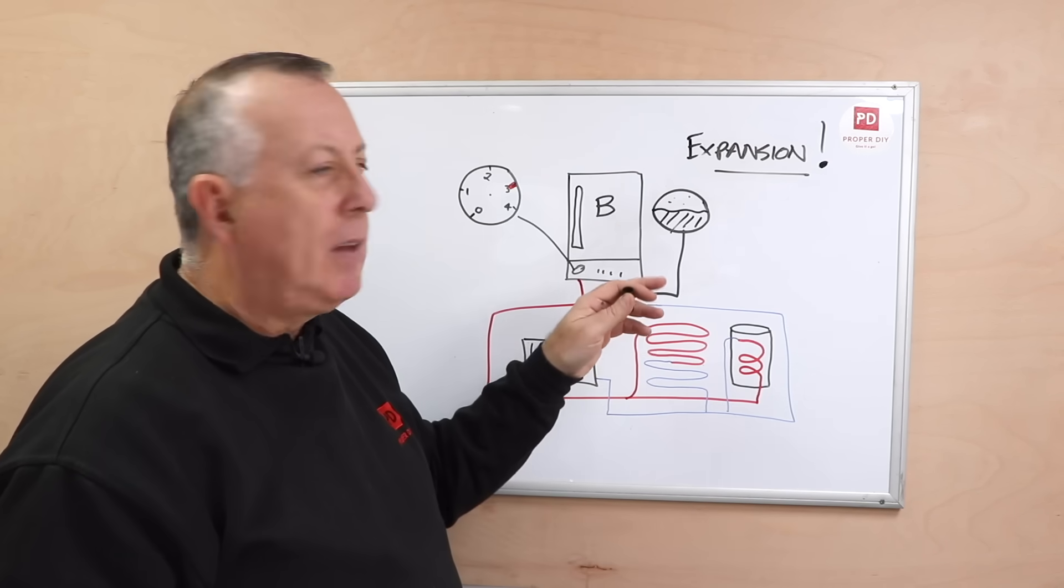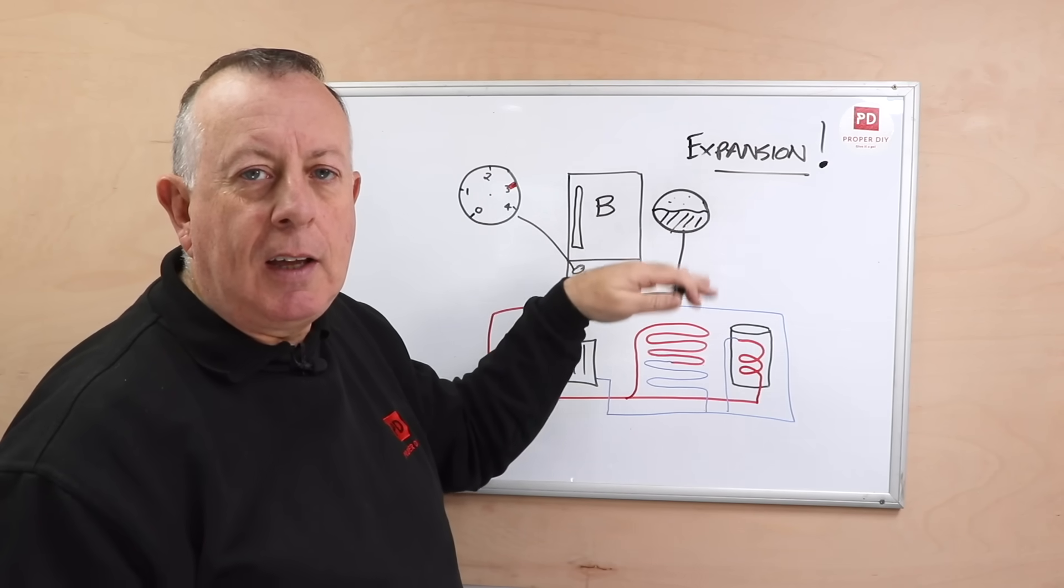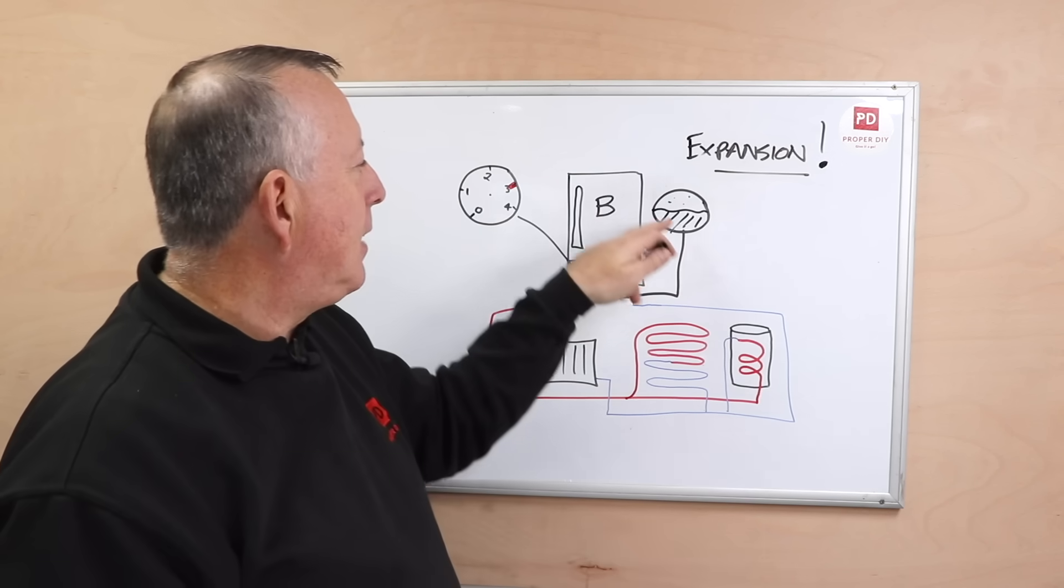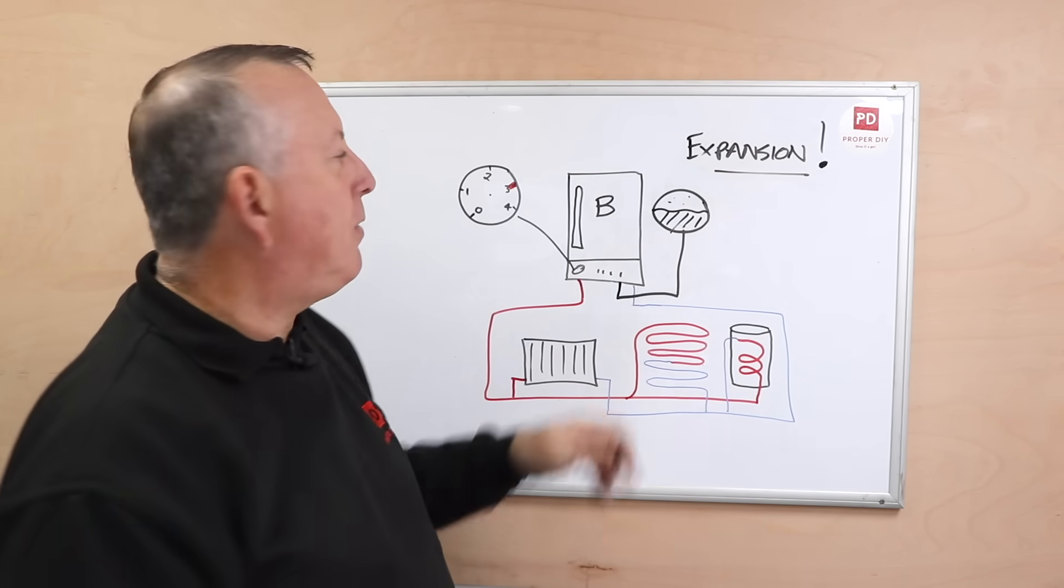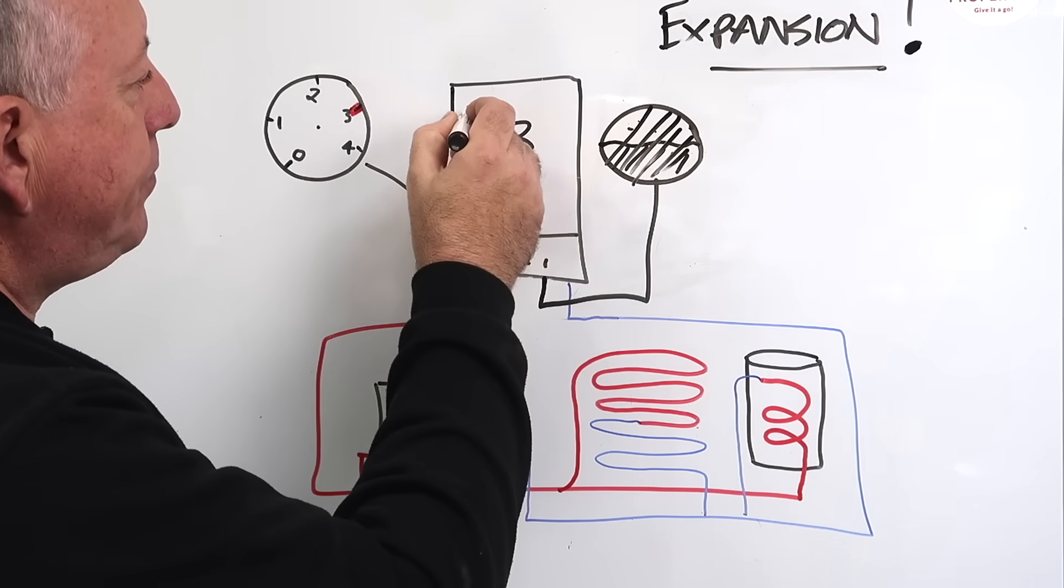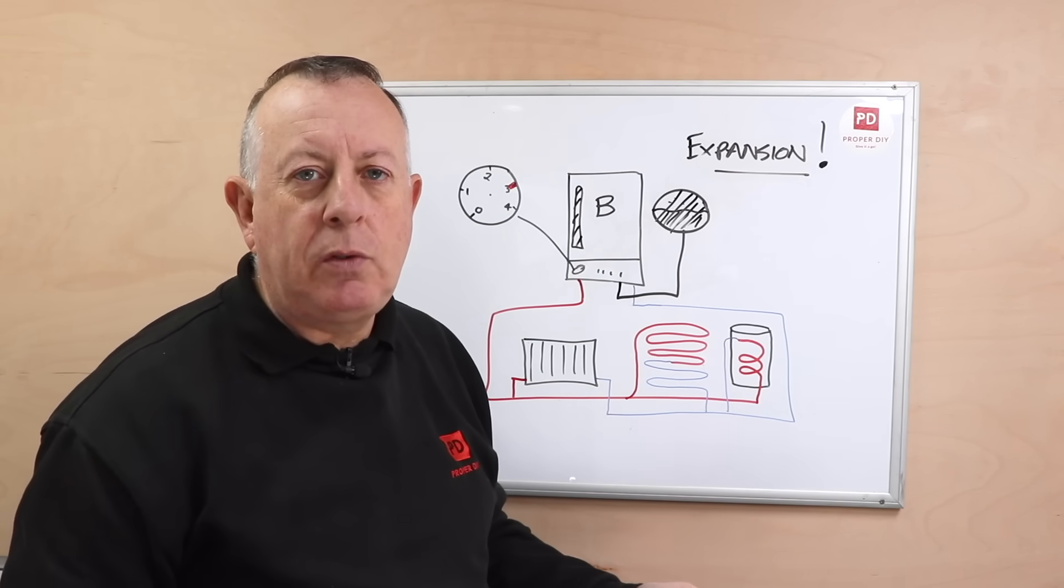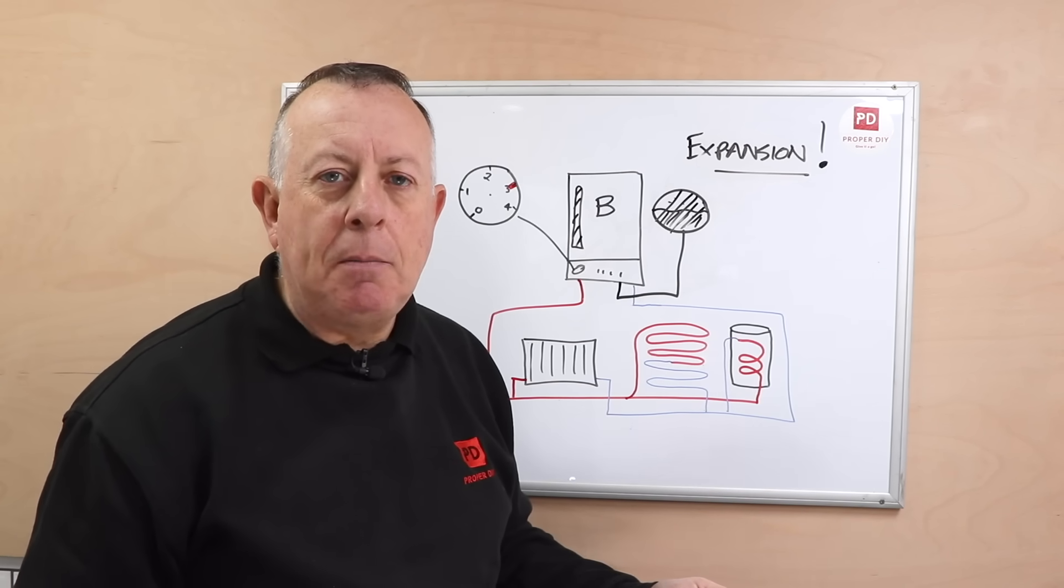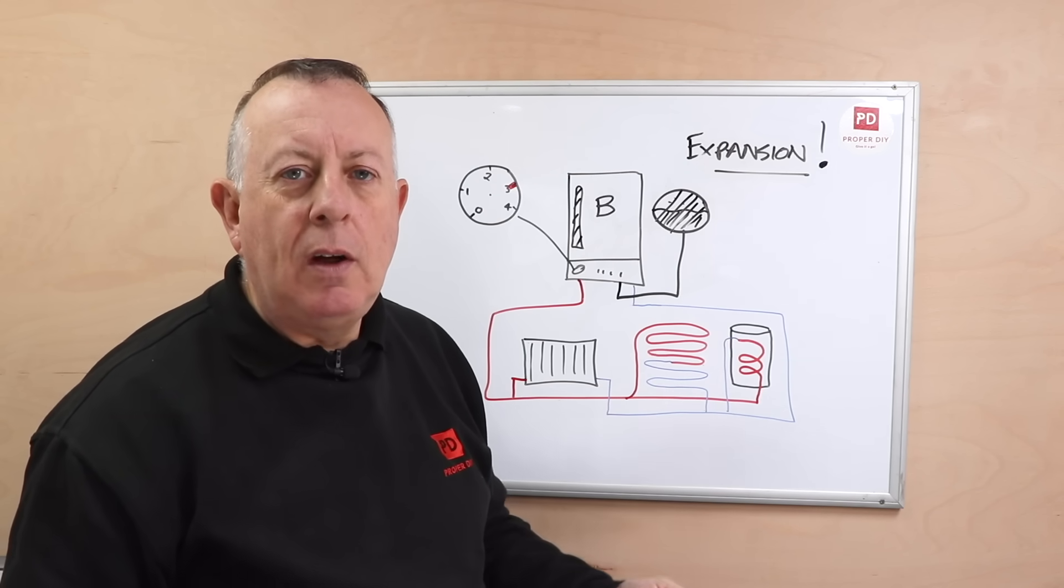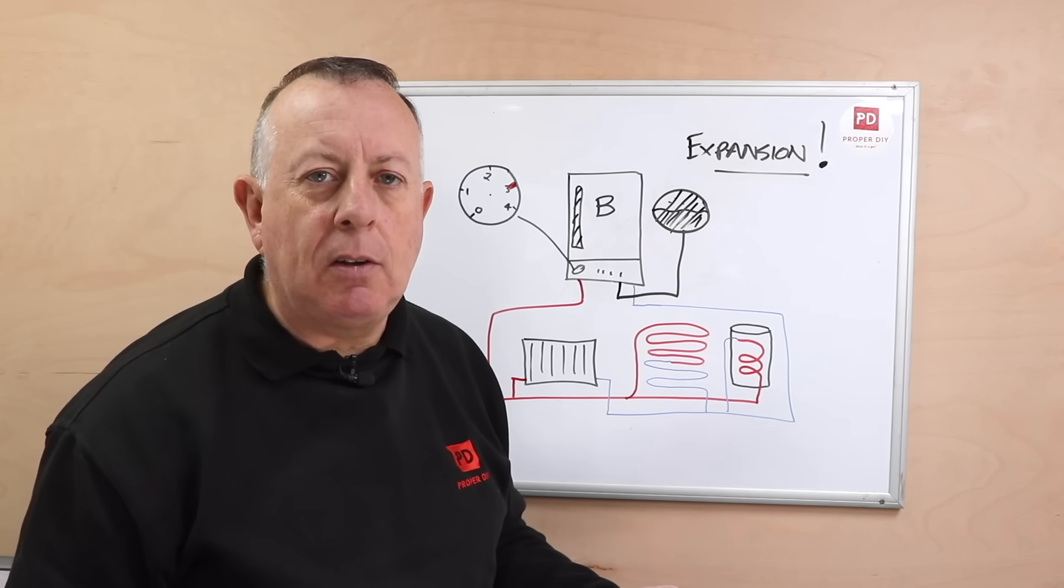Now how can an expansion tank lead to lowering the pressure of our system? Well the membrane that's in an expansion tank moves continuously in operation, so it's quite common in time that this membrane can fail. And if it does fail, essentially water will fill that tank. Once the expansion tank is full of water then it can't expand anymore, so we have a problem with where does the water go.